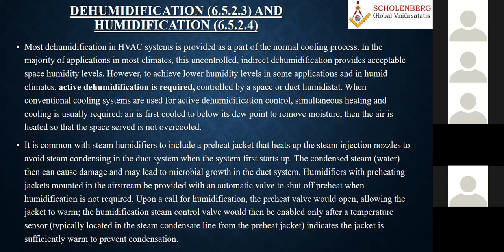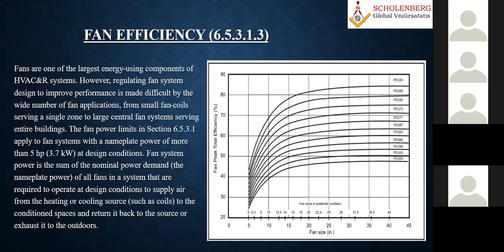Because most of the time when you include a humidification system, particularly in clean room areas, you need to be very, very careful in the design for operation. And AHU manufacturers also need to have a check mechanism at all the stages. Otherwise, if you ignore it in one place, that will definitely have a big impact during the operation time also.